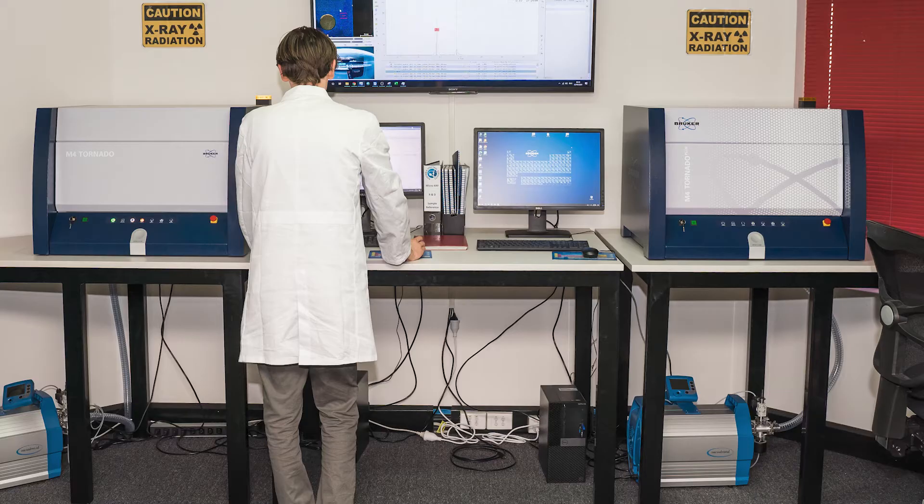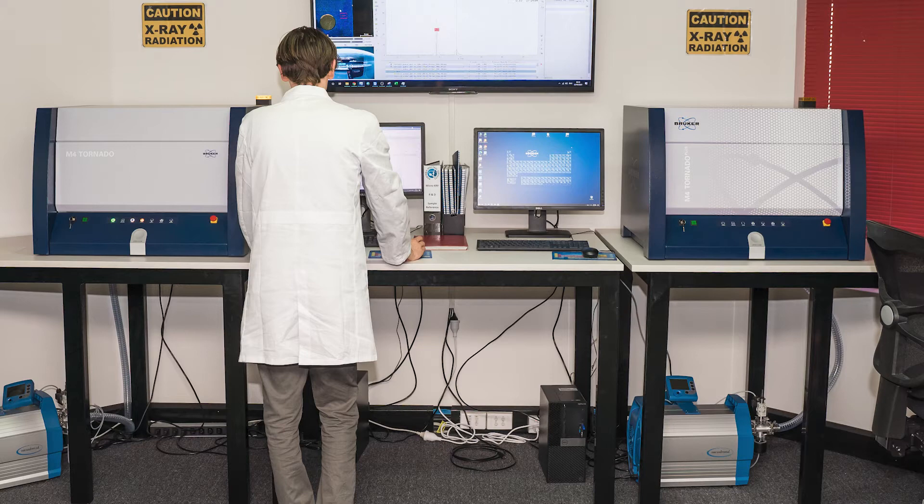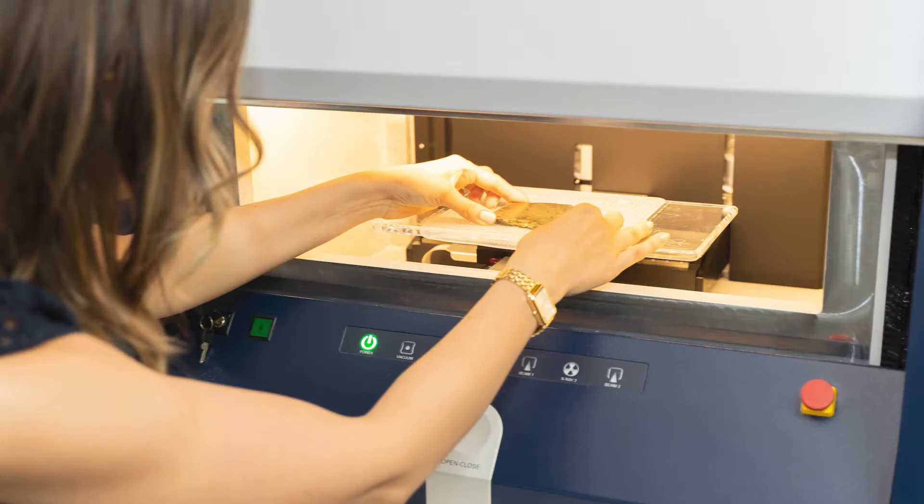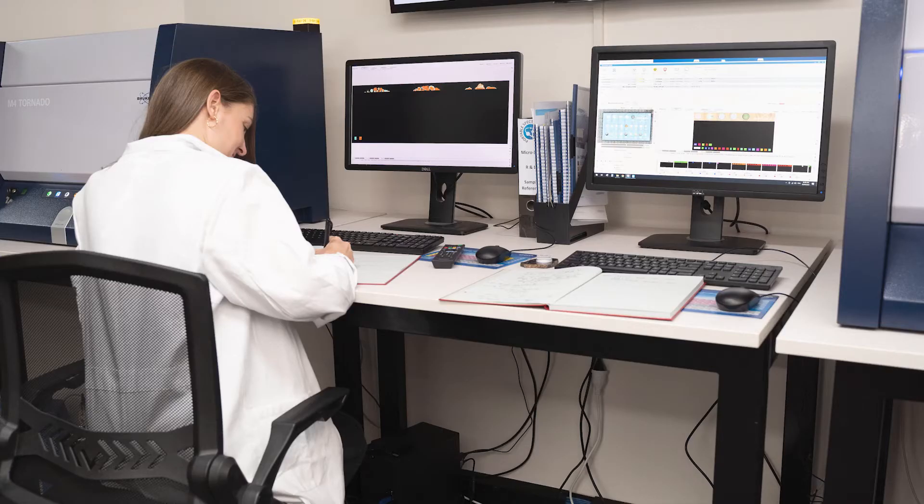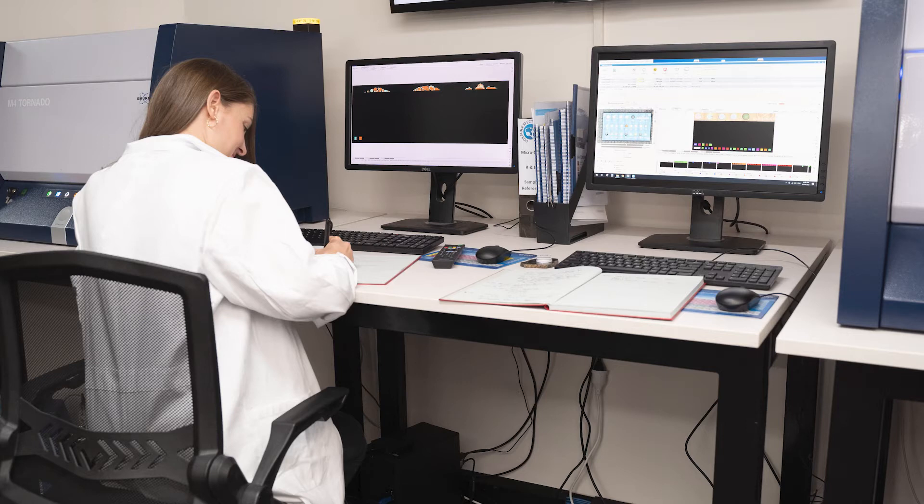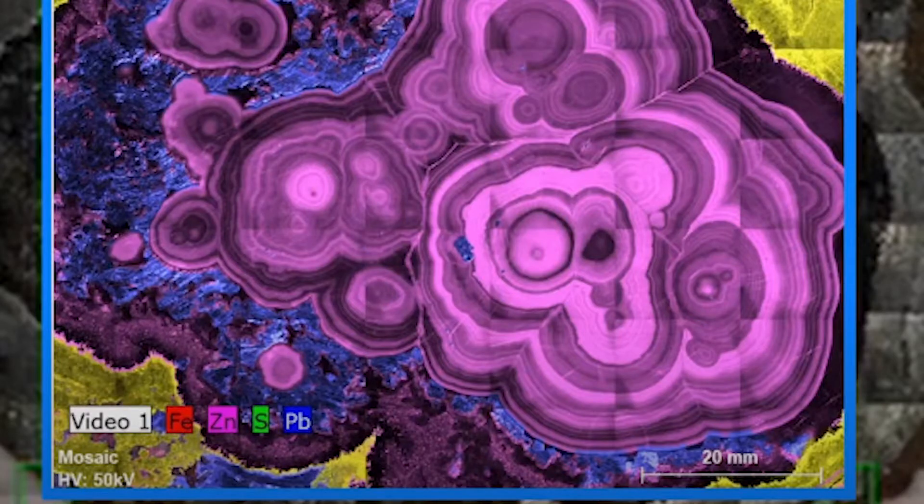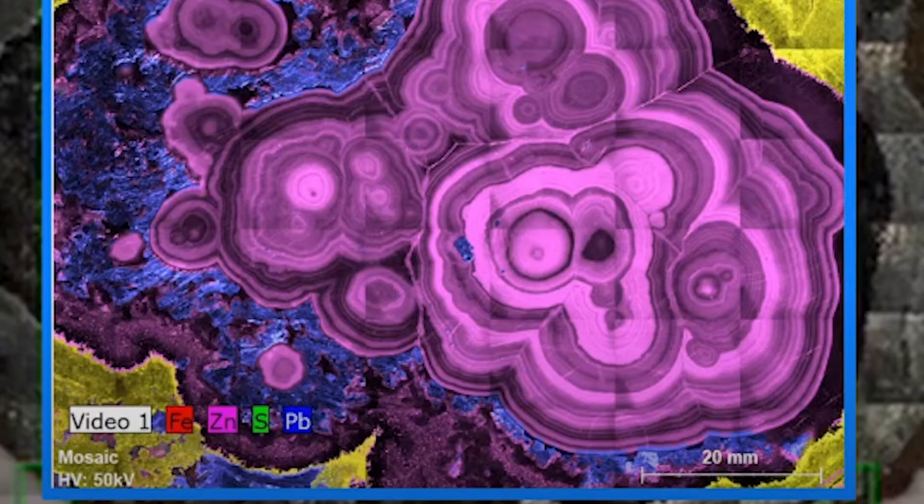Whereas for the micro XRF, we then go from looking at around three to eight millimeters down to a 25 micron spot size. So a whole different scale of resolution. And of course, we start to introduce mapping. So rather than a single spot analysis to represent effectively a whole sample, we can now analyze the full surface of the sample and actually map distribution.